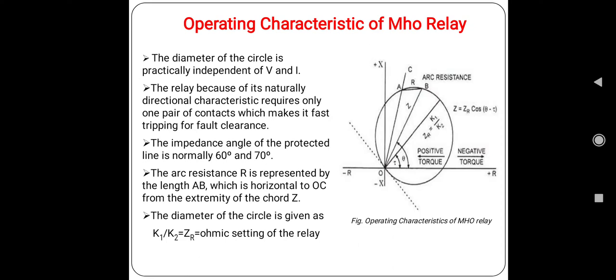By making τ equal to or little less lagging than θ, the circle is made to fit very closely around the faulty area so that the relay is insensitive to power swings and therefore particularly applicable to the protection of long or heavily loaded lines.